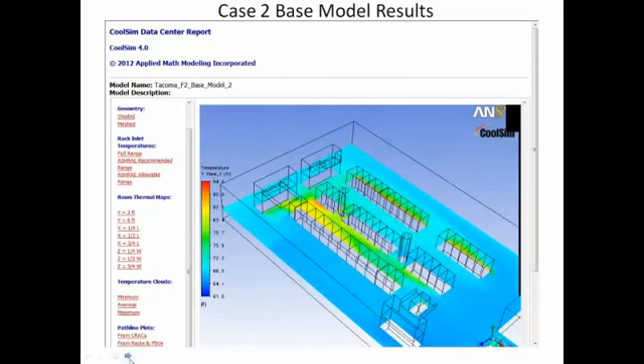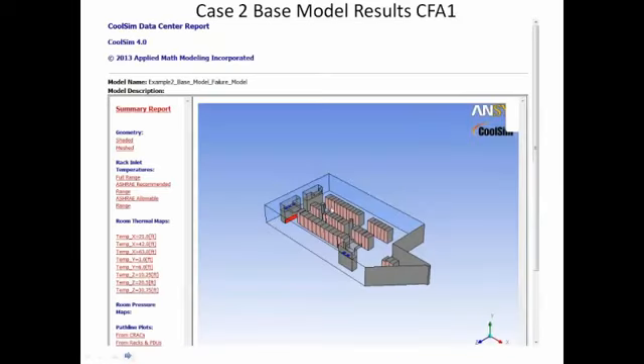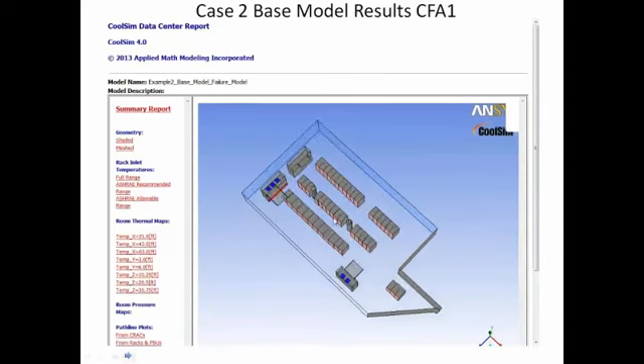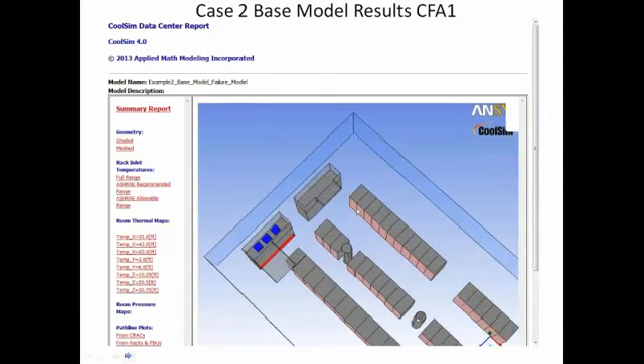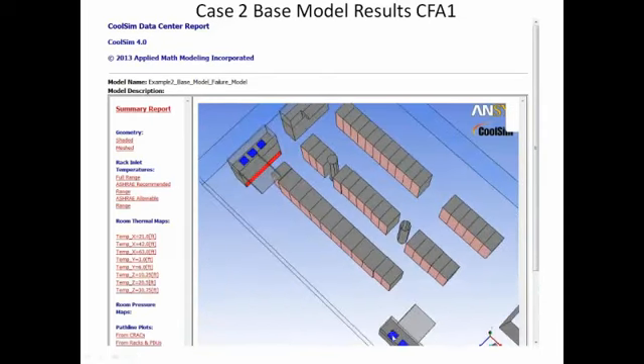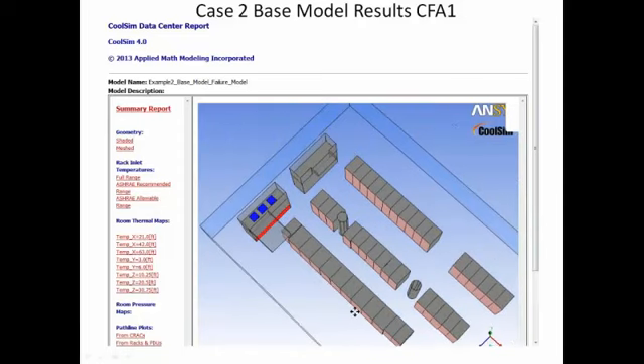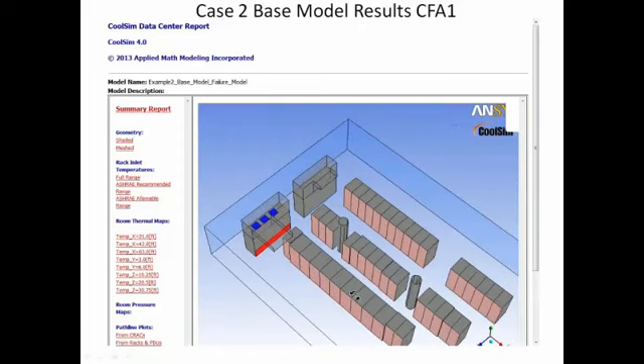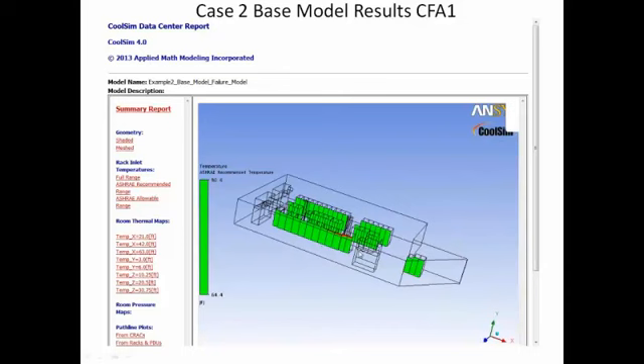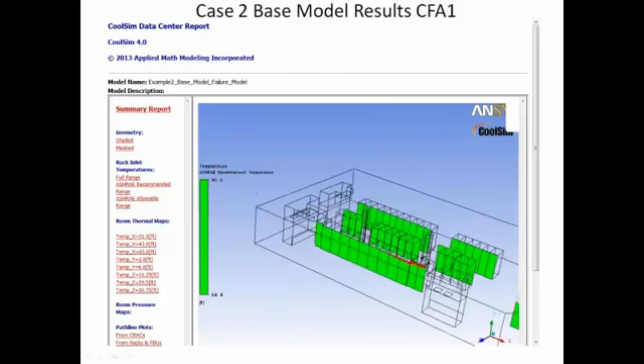And if we roll forward and say, okay, well, what happens in a failure mode here? Now, in this particular run, I'm shutting off one of the 30 tons. I'm turning on the 20 ton to compensate for it. I'm assuming these are networked together and one goes on and one goes off. You would say, well, I should be okay in this case. This one should be a fairly good case. But let's take a look at what happens. Not so bad. That one does work okay.